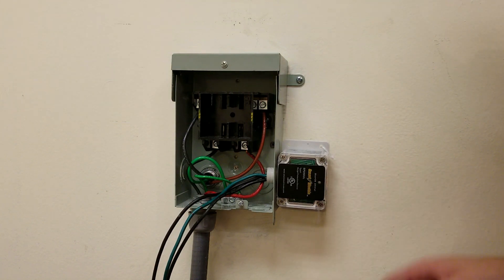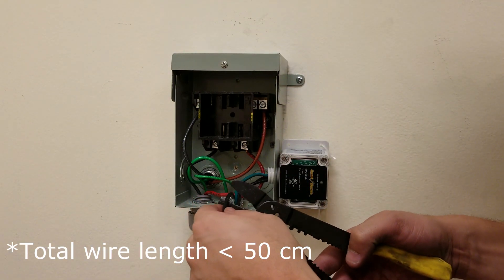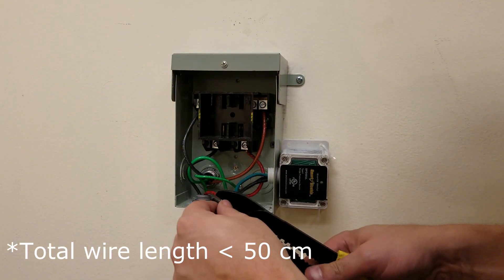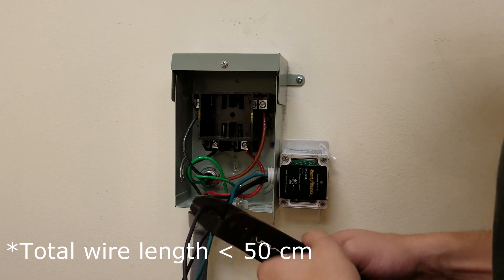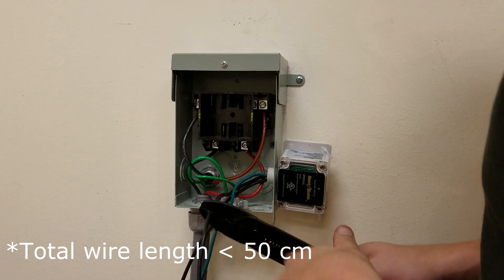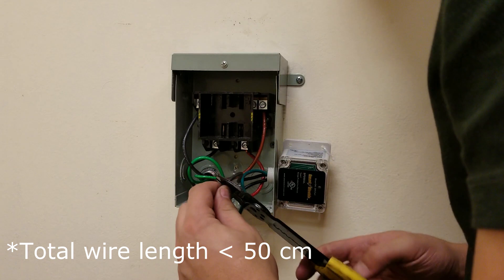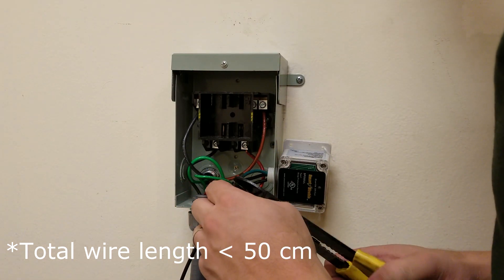Choose a mounting location that will minimize the length of wire needed to connect the SPD. Cut the wires to the shortest length possible for the installation to minimize the wiring impedance to surge currents. The total length of the connections of the SPD to the network and ground terminal block should not exceed 50 centimeters.